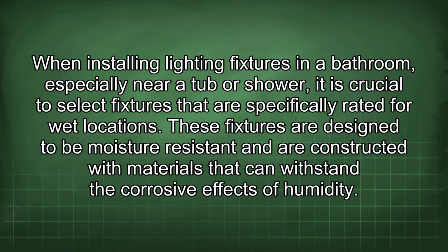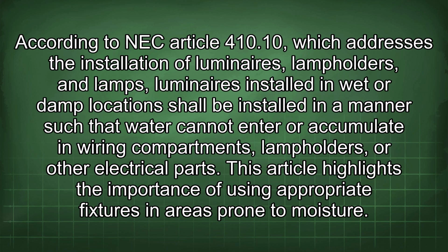These fixtures are designed to be moisture resistant and are constructed with materials that can withstand the corrosive effects of humidity. According to NEC Article 410.10, which addresses the installation of luminaires, lamp holders, and lamps, luminaires installed in wet or damp locations shall be installed in a manner such that water cannot enter or accumulate in wiring compartments, lamp holders, or other electrical parts. This article highlights the importance of using appropriate fixtures in areas prone to moisture.